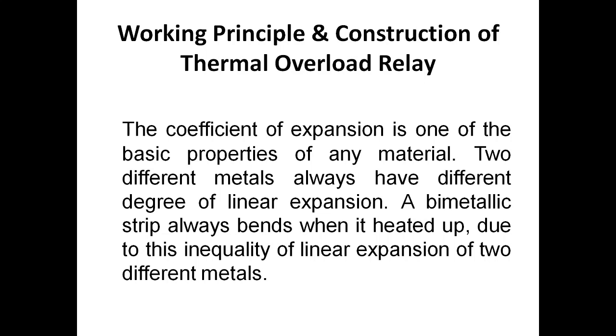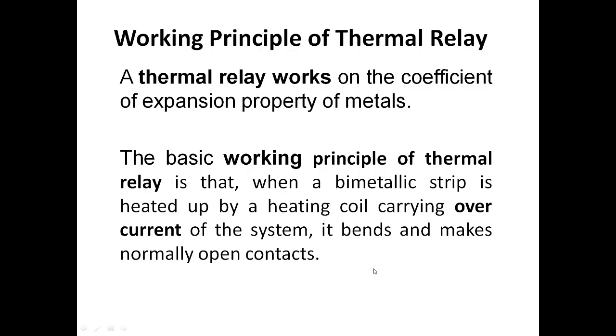The coefficient of expansion is one of the basic properties of any material. Two different metals always have different degrees of linear expansion. A bimetallic strip always bends when it is heated up, due to this inequality of linear expansion of two different metals. Working principle of thermal protection relay.